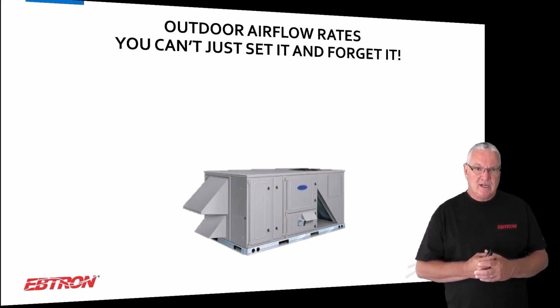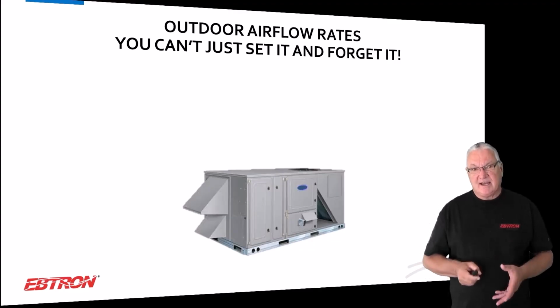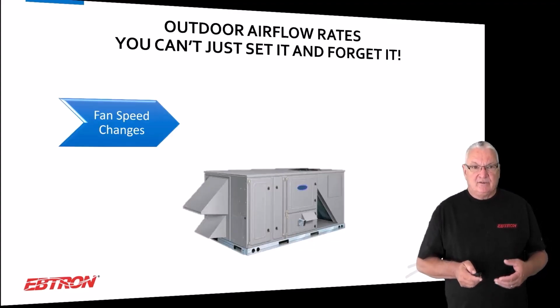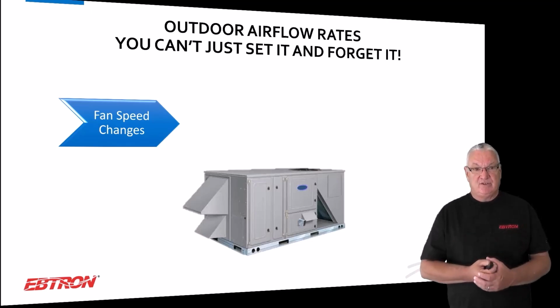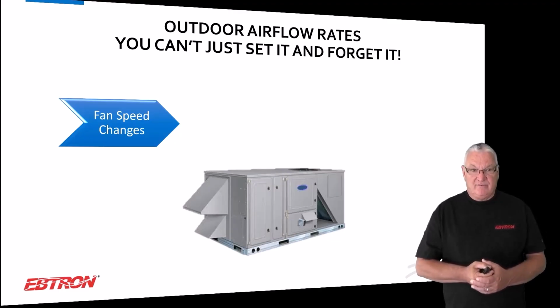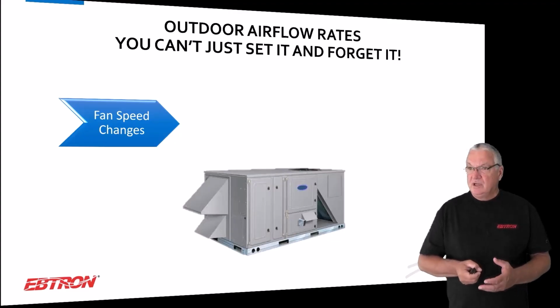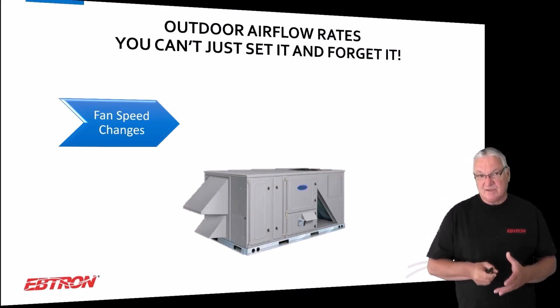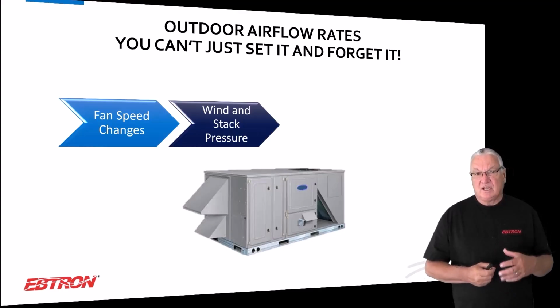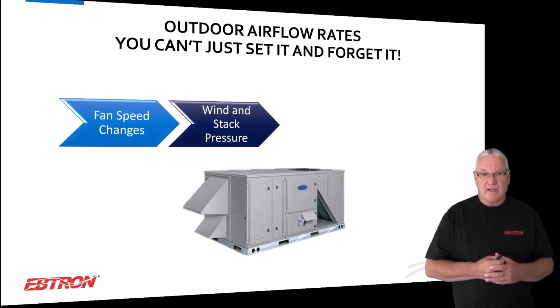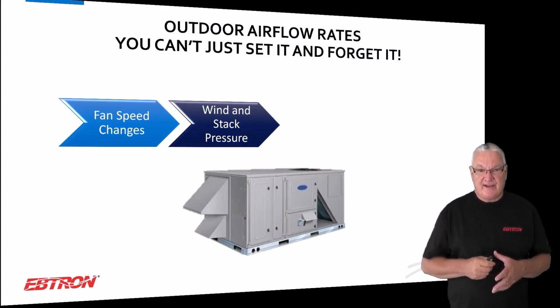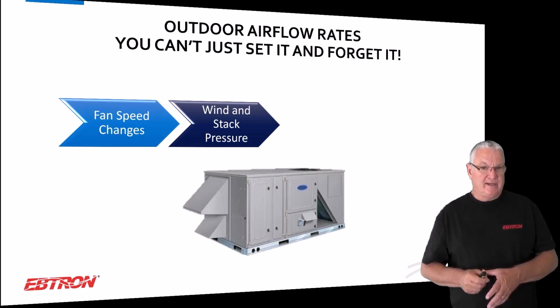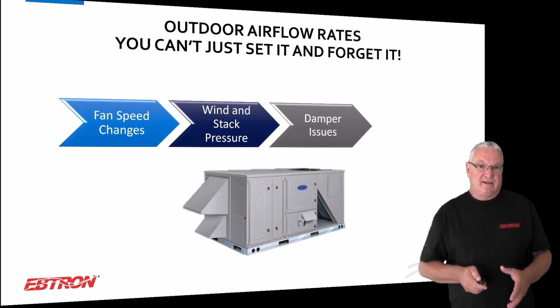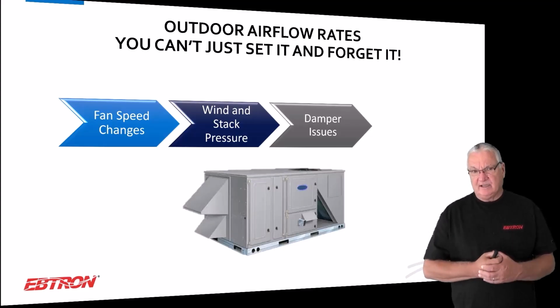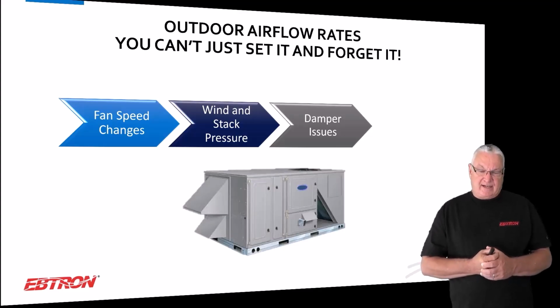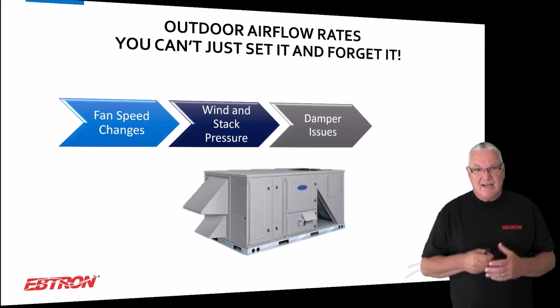Okay, outdoor airflow rates are going to be something that you just can't set and forget, and there's reasons for that. All right, and the reasons for that can be, we could have fan speed changes. Okay, we could have systems that are VAV in nature, or even if we have some dedicated outdoor air systems, there's kind of some similarities there too. But the thing that gets overlooked a lot is wind and stack pressure. What's going on the outside of the building, and how do those pressures affect the amount of outdoor air that's actually coming into your unit? Okay, I think it's fairly significant, and I want to show you that. All right, and then if we're talking about air handling units, we also have to deal with dampers, and the fact that there are a lot of issues with dampers. And so it's not a set it and forget it type of thing.